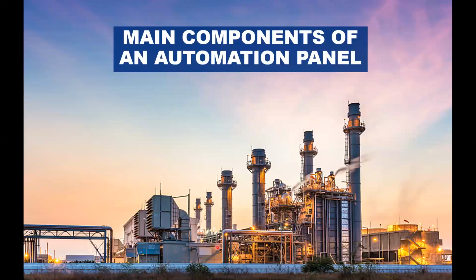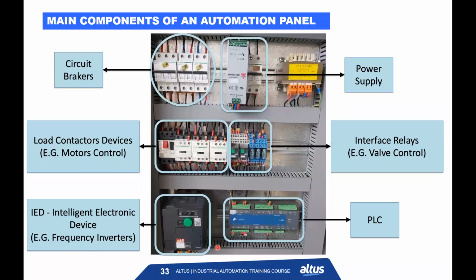The main components of an automation panel consist basically of these: circuit breakers to supply the AC voltage here and to feed and supply the power with AC. This power supply just converts the AC voltage to DC 24. Load contactors here are devices, for example, for motor control, where the command is sent from the PLC, of course, and the power goes to the motor.